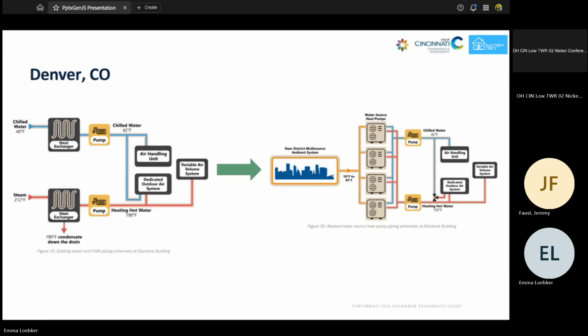This is an example of what they're currently considering. At a high level, they're looking at decommissioning the steam plant, or potentially decarbonizing it through an alternative means, and leaving that as an option. But they're also looking at repurposing the existing chilled water system and converting it into a district ambient loop—so rather than a series of hot water and chilled water pipes throughout the entire city, you'd have a single pipe with neutral water temperature circulating through every building. At the building level, each individual building would have its own water source heat pumps or equivalent equipment to access that neutral loop and provide heating and cooling within the building. One benefit is that it gives building owners a lot of flexibility. Also, switching to a single pipe system reduces a lot of the capital cost of running new infrastructure through a big urban region.